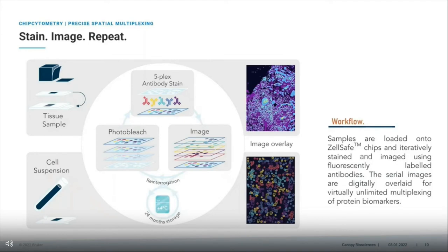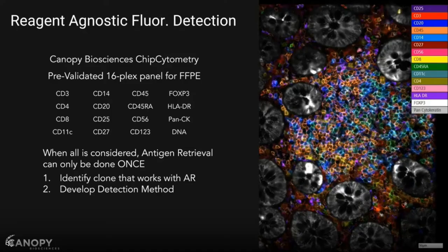Starting with an overview of what we physically do with these samples: we can look at either a cell suspension or alternatively a tissue sample — essentially anything that you can section and put onto a slide, or anything you can pipette. We then go through rounds of five-plex iterations where we stain with five antibodies at a time, image, photo bleach, and image again. At any point in the cycle, you can pull the sample off the instrument and actually store it. For cell suspension, we've done validation data showing storage is actually up to 36 months, because we're using base fluorescence.